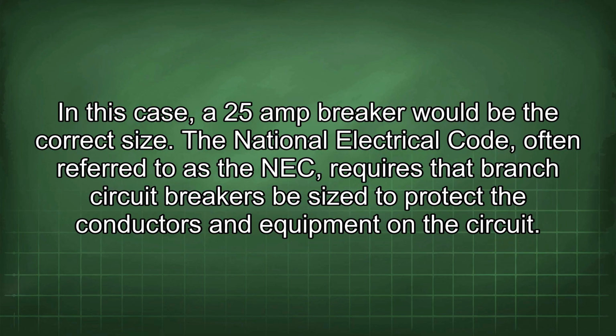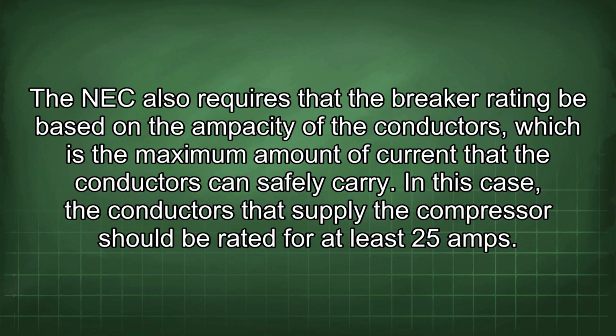The National Electrical Code, often referred to as the NEC, requires that branch circuit breakers be sized to protect the conductors and equipment on the circuit. The NEC also requires that the breaker rating be based on the ampacity of the conductors, which is the maximum amount of current that the conductors can safely carry. In this case, the conductors that supply the compressor should be rated for at least 25 amps.